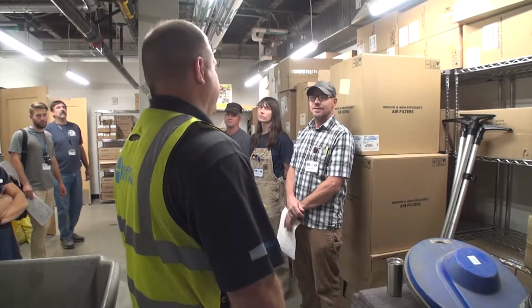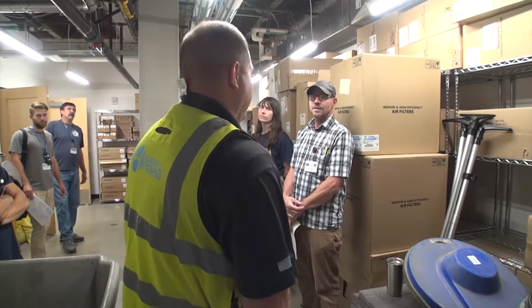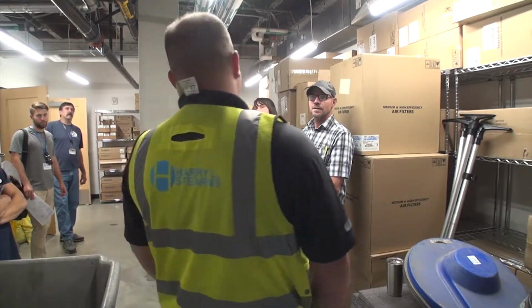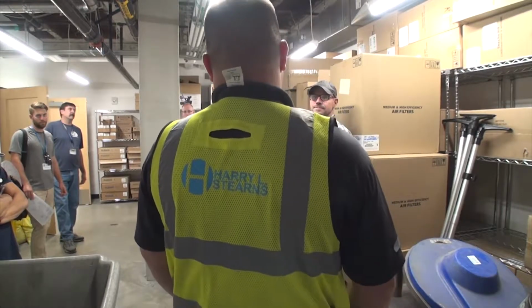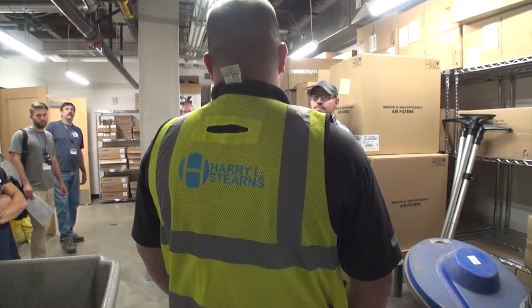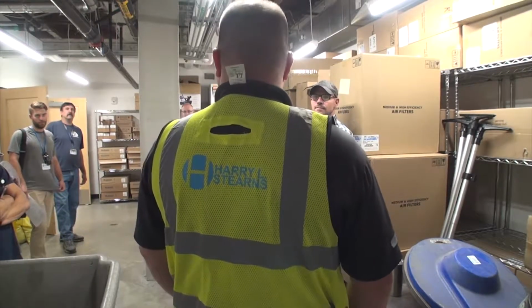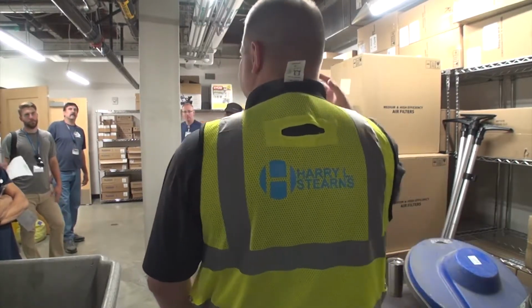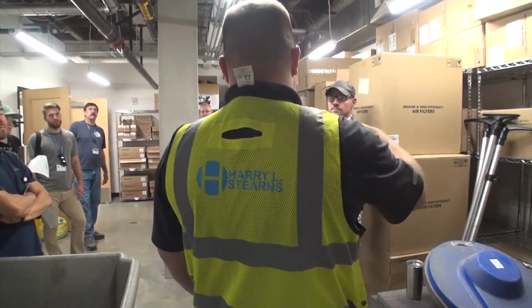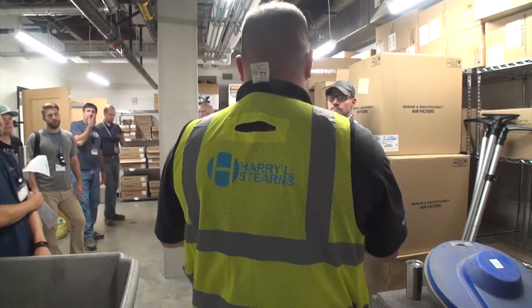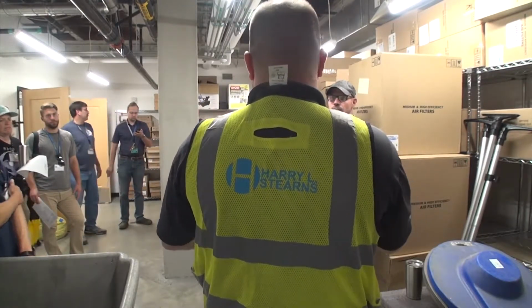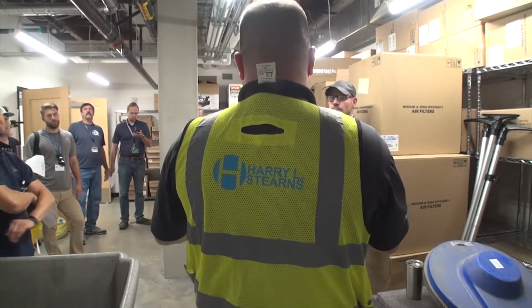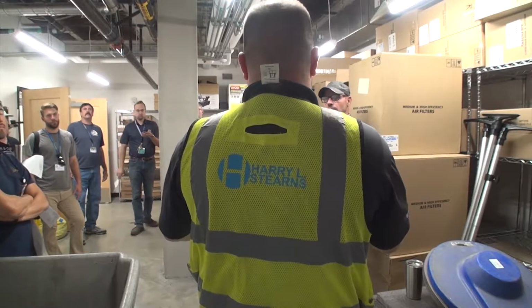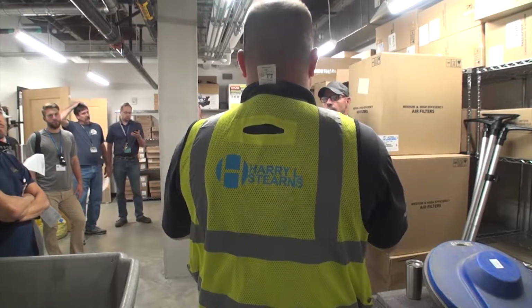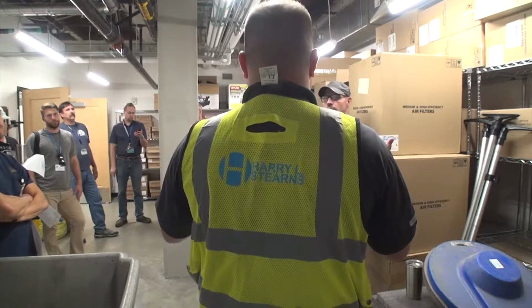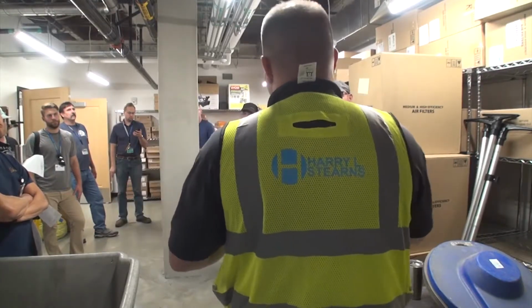Since 2014, the Oregon Energy Efficiency Specialty Code dictates that you cannot use night lights. The egress lighting you guys are used to as night lights in your building has to be controlled by an occupancy sensor, by a time clock, or by means of a third-party integration to a device that confirms the building is occupied, like a security system.